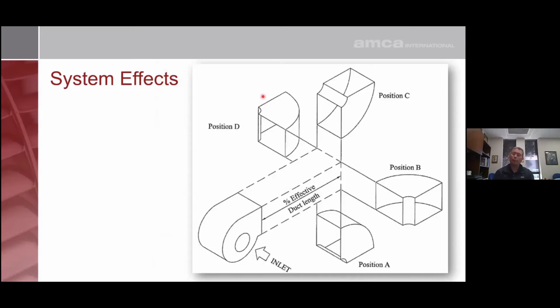If you have to have elbows, you have space constraints out in the field, some elbows are way better than other elbows. A position A elbow, really good. Air hugs the outside of the volute shape, continues along the outside of the elbow, and then you can have your straight run of ductwork afterwards to allow for static pressure regain. If you have your position C elbow, air hugs that outside volute shape, deadheads against the back of this elbow, has to get re-accelerated out. You will have some substantial losses with that.